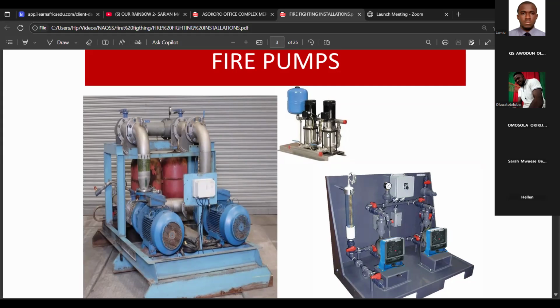What I mean is that the pipe has already exceeded its elasticity. Elasticity means something that can withstand just 4 to 7 bar, and now you put it on 9 bar. Immediately, you just see an explosion, which is very, very dangerous. Now, you put in your specification: install schedule seamless pipe, either schedule 40 or schedule 80. But like I said, I usually recommend schedule 80, based on all these fire line bursts, as in your black steel being put on pressure and all of a sudden bursting. So I usually avoid that.